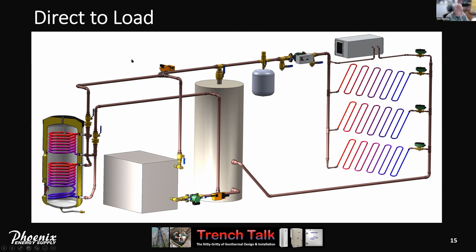So when you get a call, it's first priority to heat domestic. And both three-way valves will shift. So we're going to go up over to the heat exchangers, come back through the three-way valve, and the heat pump simply will serve this little runaround loop going and heating the domestic hot water.